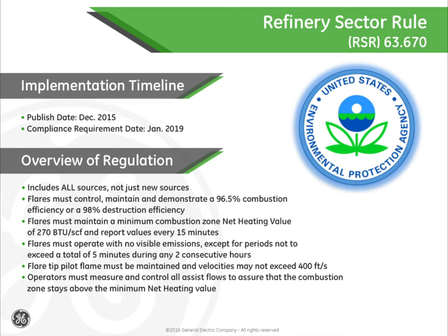This regulation can be broken down into four parts, with one main goal of efficient combustion at the flare tip. The regulations require the refinery to maintain a net heating value of 270 BTUs per standard cubic feet in each 15-minute block average of operation. They must maintain smokeless operation with no periods of visible emission exceeding 5 minutes in any 2-hour window, and maintain a tip velocity of less than 400 feet per second at all times, or as defined by the BTU content of the flare gas. And most importantly, they must automate and control all assist flows to the flare tip. This would include supplemental gas, steam, and air, if applicable.